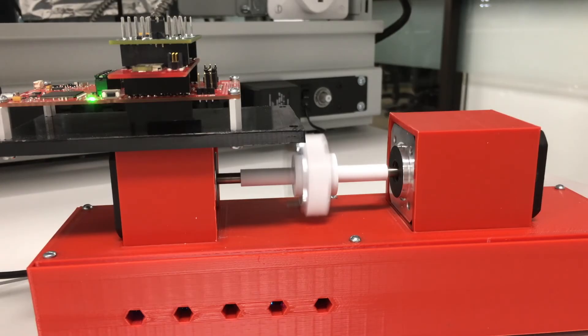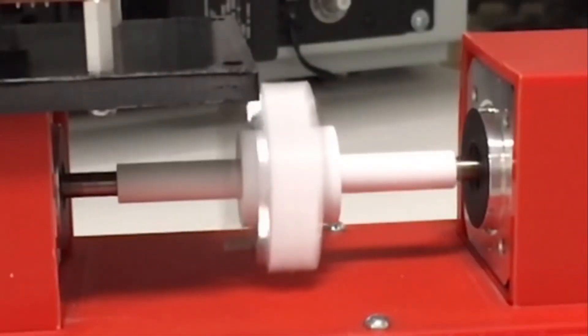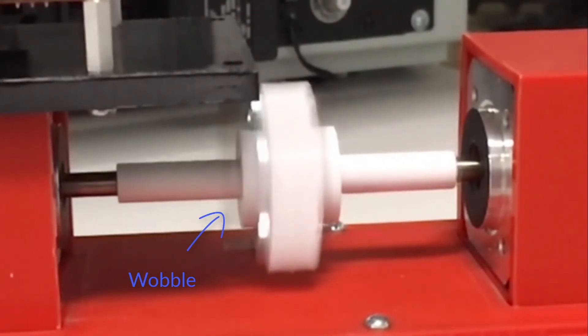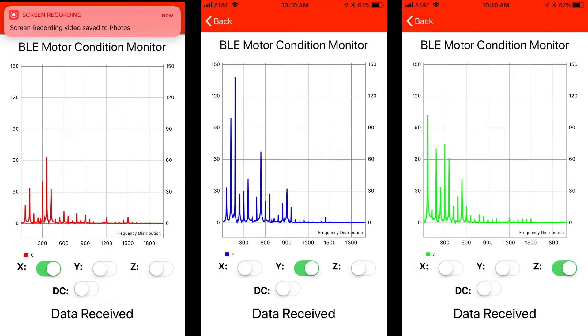Next, we shall look at a failing setup for the same motor. There is some change in the audible noise output, and the signal looks different on the scope. When we slow down the video, we can see that the shaft is wobbling about its own axis. However, the difference is not visible in the time domain but in the frequency domain.